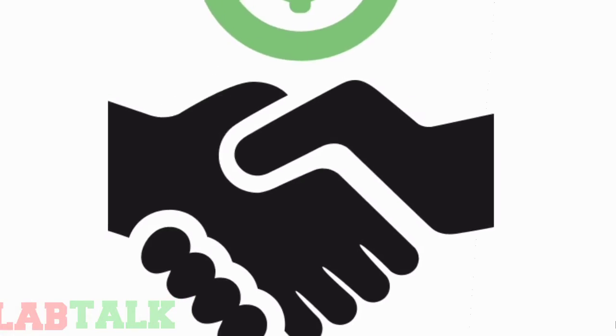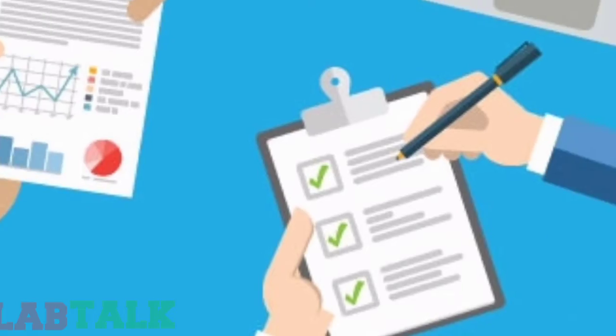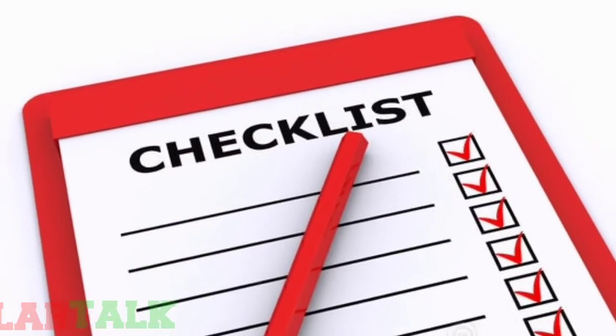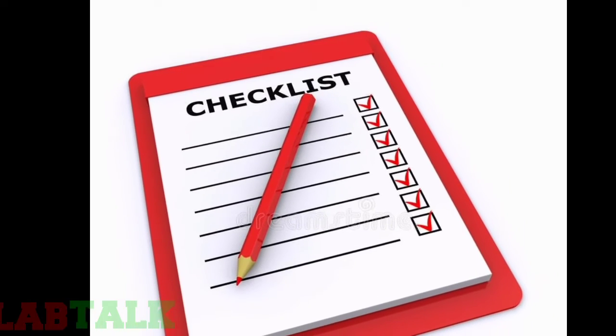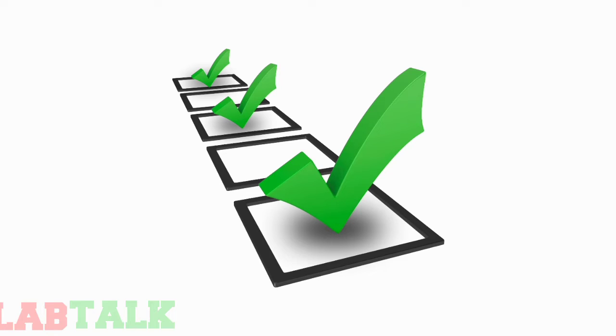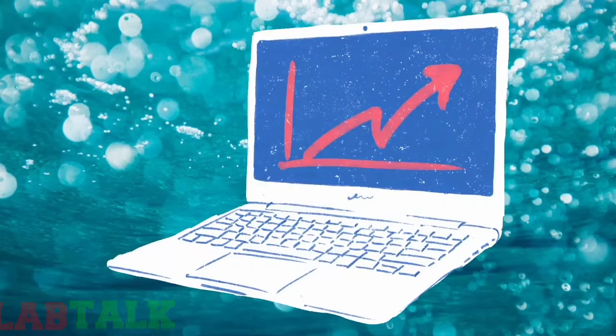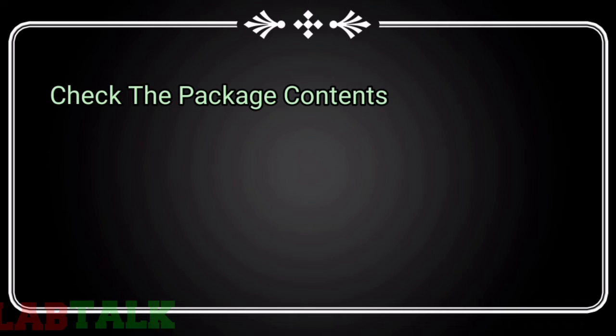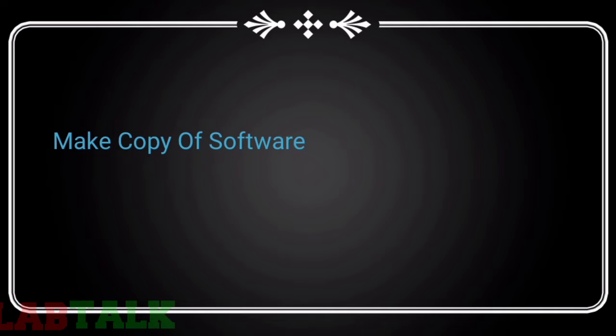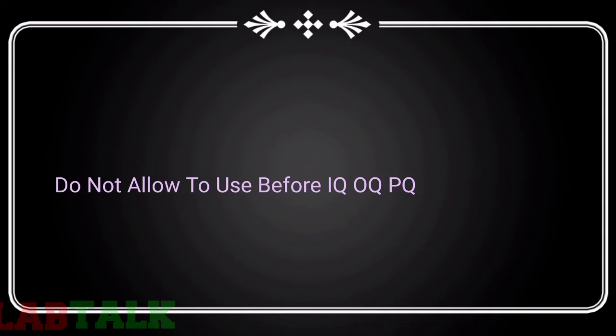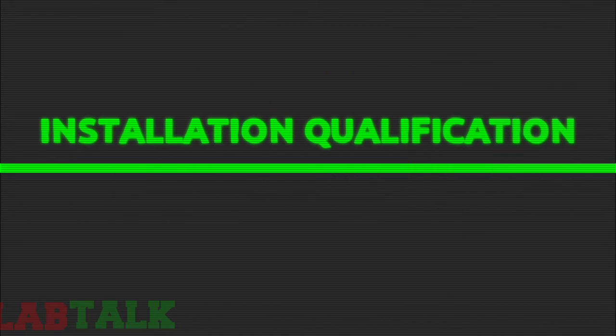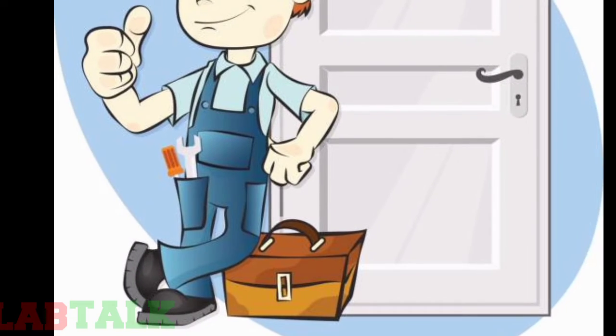The vendor's responsibility for installation should be confirmed in writing prior to the beginning of the installation process. A checklist of the expected performance specifications should be developed so that performance can be quickly verified as soon as the equipment is installed. Regarding this performance verification checklist, we will see in detail in design qualification. If the equipment is installed by the laboratory, check that the package contains all the parts. Make a copy of the software that is a part of the system. Do not allow the equipment to be used before it is completely installed, performance is verified and testing personnel are trained. So we will start with the installation qualification of the equipment in the laboratory.